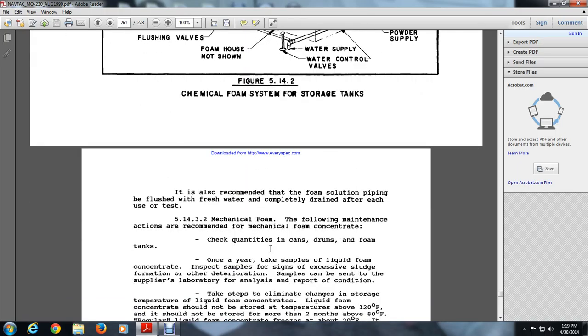Foam storage tanks. It is also recommended that the solution piping and flushing fresh water be completely drained after each use. 5.14.3.2, test of the mechanical foam. Following the maintenance actions recommendation for mechanical foam concentrate: check chemical quantities in cans and drums and foam tanks once a year, and take samples of liquid foam concentrate. Inspect samples for excessive sludge and formation of other deterioration.